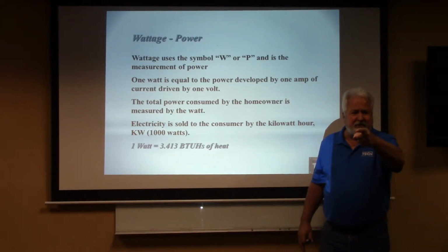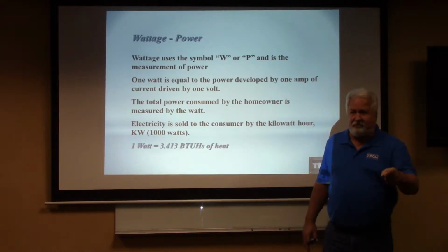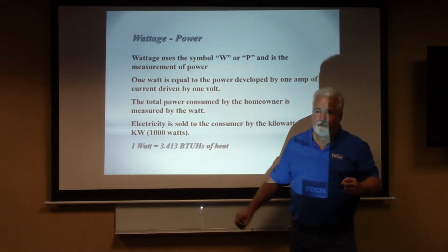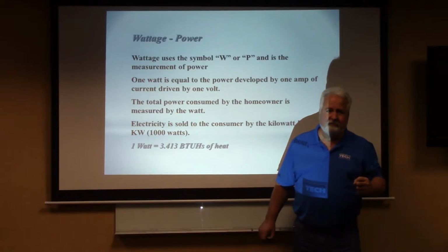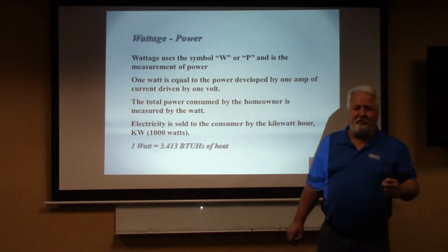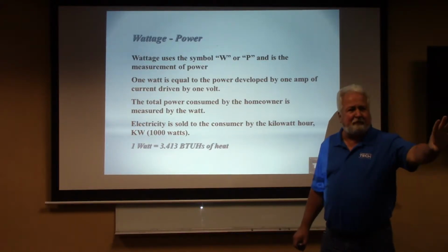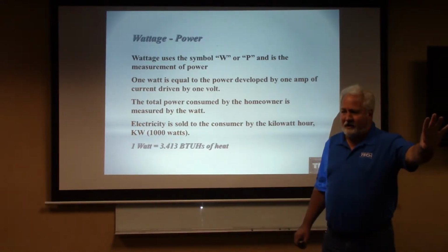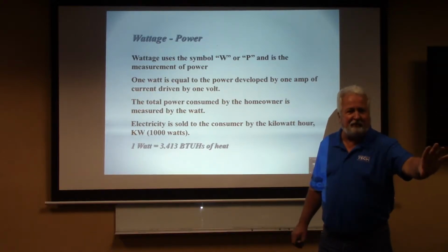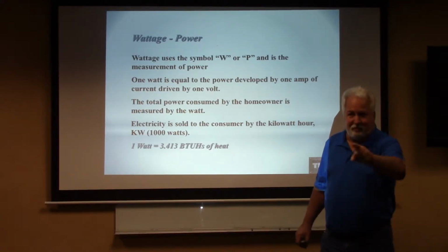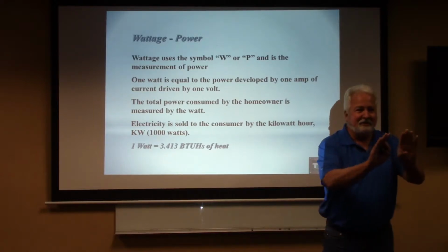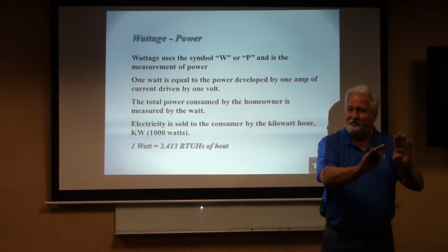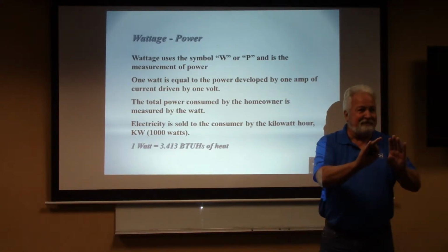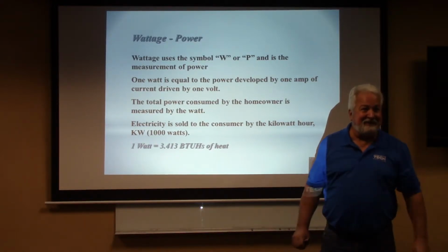Somebody break out your calculators, because I know you have them on your phones. Your 10 kW is 10,000 watts. 10,000 watts times 3.413 is 34,130, so about 34,000 BTUs. So when we flip into defrost and start cooling at 36,000 BTUs in the house, we just brought on 10 kW, which is 34,000 BTUs of heat to compensate for that cooling taking place right there. Does that make sense? Now it does.